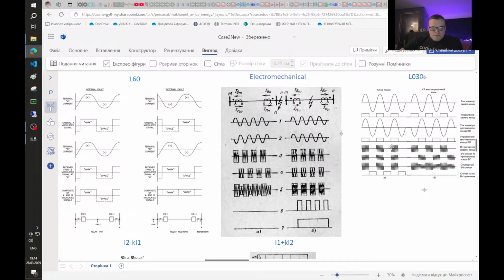So the main thing is they have a lot in common. From this part you can see faults that are located on the protected object and external faults, but on the electromechanical picture that shows how the electromechanical relay works, it will be different. So here you can see the external fault, but here a fault on the protected object. You can see that the main difference is that it compares the phases of the signals, and in case of a fault on a protected object, there will be pauses in the current on the output of the transmitter receiver.